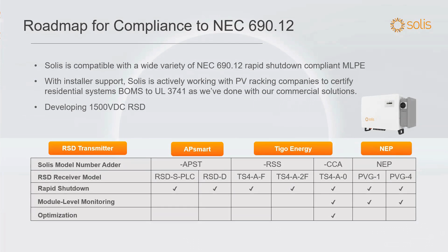I want to show you here a little later, but this kind of thing, I know it shows rapid shutdown on module level, and it really isn't required in Canada at all, but it does show a little bit about the flexibility we're seeing from these little companies that are starting up developing module level power electronics. NEP is a good example there, where they have a rapid shutdown unit, but they also have module level monitoring, and they can report the temperature of their devices and shut down if it gets too hot. These sorts of little extra things you get without having to install a big power supply or anything in these devices really add some interest, I think, to the PV string level platform.